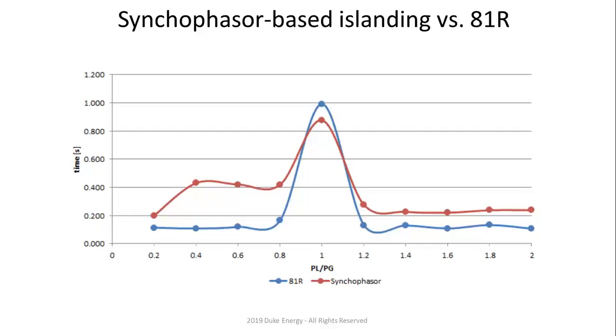The reason is that the 4-way switchgear that we originally installed is built only for 2,000 operations. So when you operate the switchgear 3 times past its operating life, certain things get slowed down. You probably wouldn't see it this slow, but you can clearly see that we can still detect islanding based on both of these methods. And as expected, synchrophasor-based islanding is the fastest one with PL over PG equal to 1. But again, just note that this particular testing was done probably about 2 months ago.